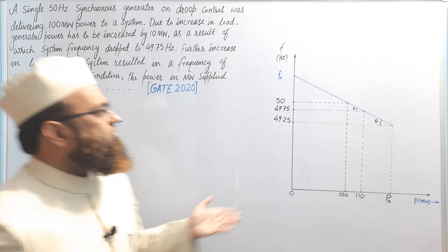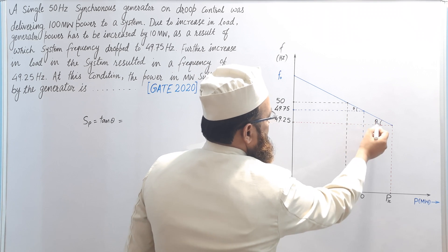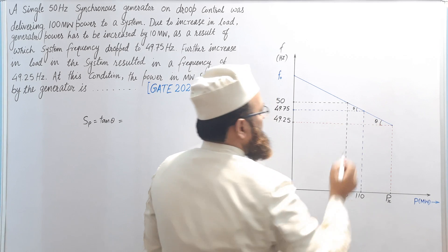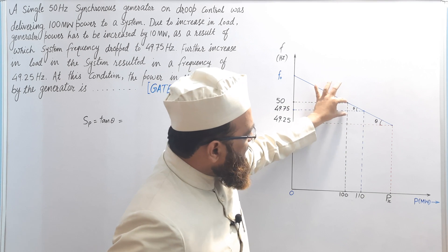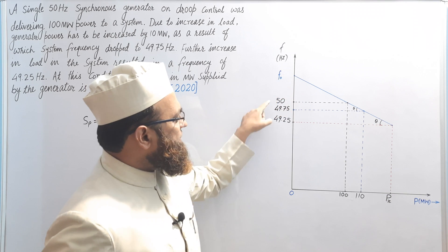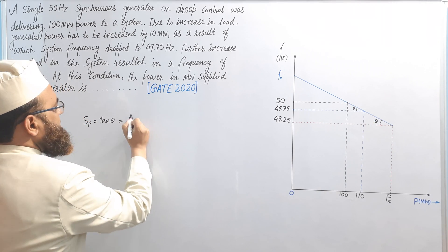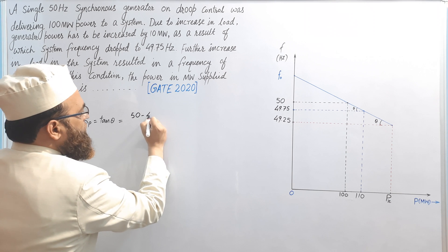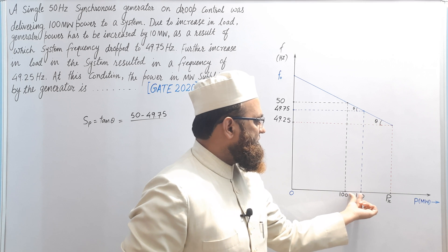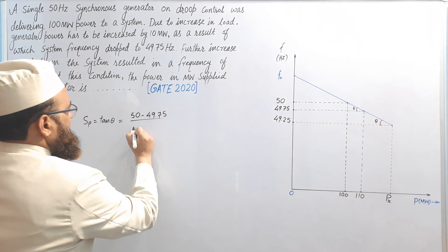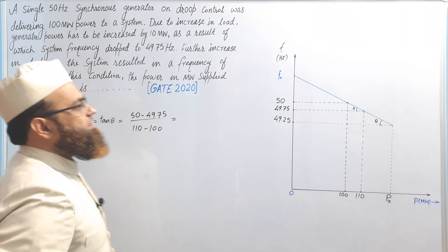We may evaluate tan θ from any of the triangles formed so far. Let us take the smaller triangle first. If this angle is θ, then in this right-angle triangle, the slope tan θ equals perpendicular upon base. The perpendicular is the difference of 50 and 49.75, and the base is the difference 110 minus 100 megawatt. So tan θ equals (50 − 49.75) upon (110 − 100).